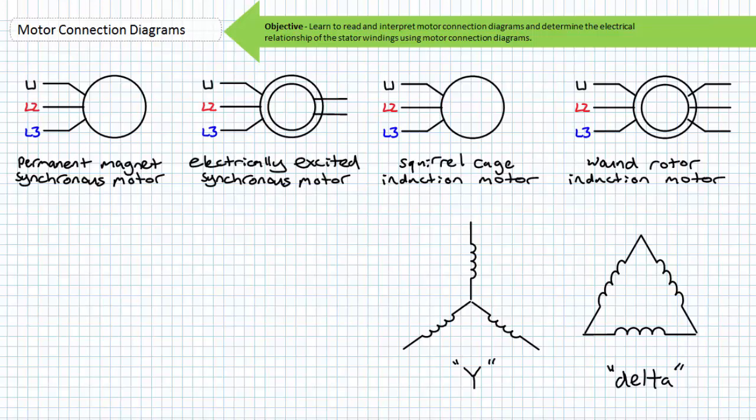Manufacturers offer dual voltage motors so their products can meet the needs of industrial applications in various countries characterized by different electrical distribution voltages. Long story short, you get 0 points for creativity. Follow motor connection diagrams exactly as illustrated, otherwise serious repercussions may result.